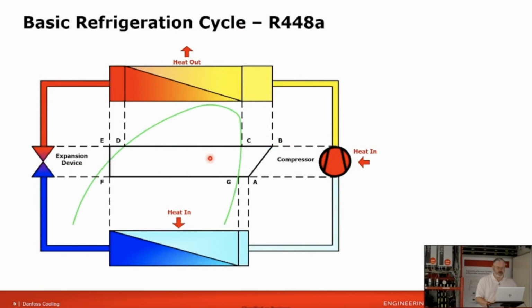So we're going to start just by reviewing a basic R-448A refrigeration cycle, just to kind of wet your whistle and get you back to the early days when you first talked about pressures and temperatures around the system. If we follow our friend here, at point A, we're a low temp, low pressure, superheated vapor. So this is the suction inlet to the compressor at this point. We move across the compressor, and we add the heat of compression. We're now a high pressure, high temperature, superheated vapor. And we know we're superheated because we're to the right of the dome, which means we've boiled everything into a vapor. We've hit the saturation curve. Then we've added additional heat. So at point B, we're a superheated vapor.